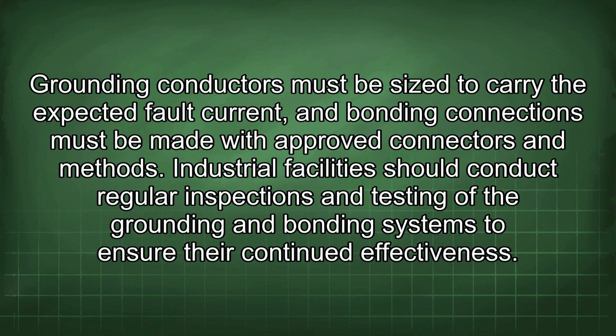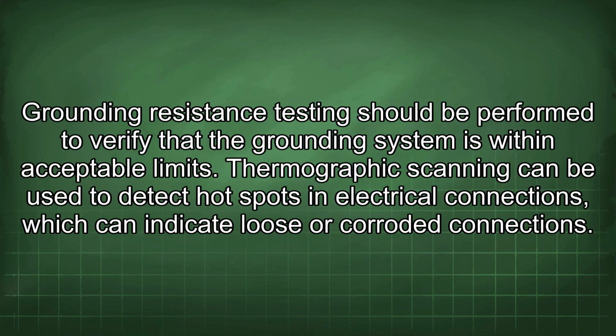Grounding conductors must be sized to carry the expected fault current, and bonding connections must be made with approved connectors and methods. Industrial facilities should conduct regular inspections and testing of the grounding and bonding systems to ensure their continued effectiveness. Grounding resistance testing should be performed to verify that the grounding system is within acceptable limits. Thermographic scanning can be used to detect hot spots in electrical connections, which can indicate loose or corroded connections.